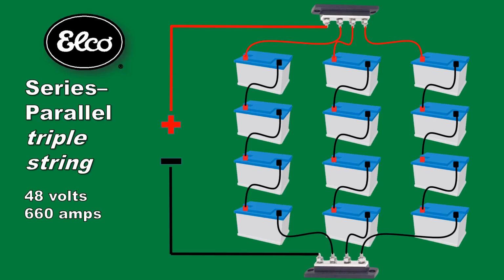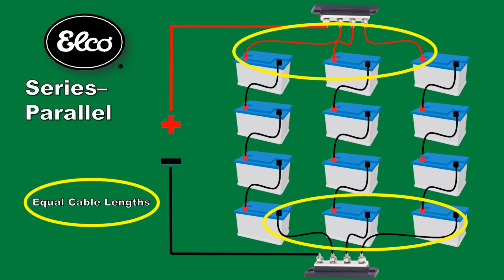Connecting one string to another in parallel is accomplished by connecting the first battery and the last battery of each string. One thing to keep in mind is that battery strings cabled together in parallel must have equal cable lengths. Even minor differences in lengths can affect the discharge and recharge rates of each battery, and over time will lead to imbalanced battery capacities. The condition will continue towards greater imbalance and will diminish the overall capacity of the battery string. When cabled correctly, you will most likely have extra cable length for batteries closer to the bus bars in order to match the cable length for batteries farthest from the bus bars.